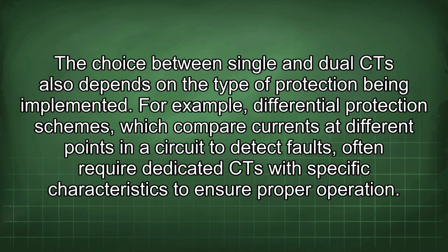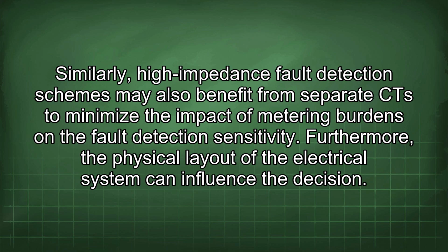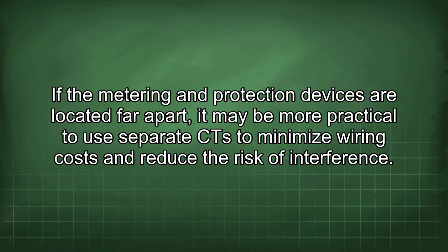The choice between single and dual CT also depends on the type of protection being implemented. For example, differential protection schemes, which compare currents at different points in a circuit to detect faults, often require dedicated CT with specific characteristics to ensure proper operation. Similarly, high-impedance fault detection schemes may also benefit from separate CT to minimize the impact of metering burdens on the fault detection sensitivity. Furthermore, the physical layout of the electrical system can influence the decision. If the metering and protection devices are located far apart, it may be more practical to use separate CT to minimize wiring costs and reduce the risk of interference.